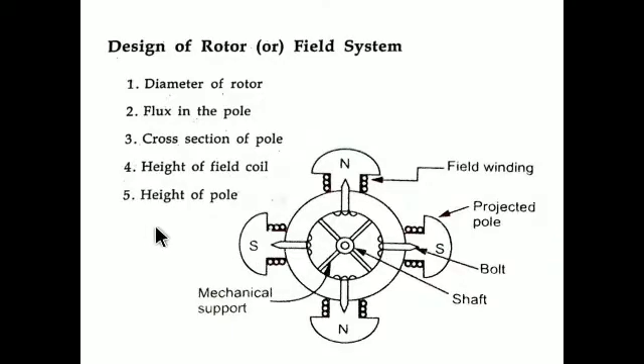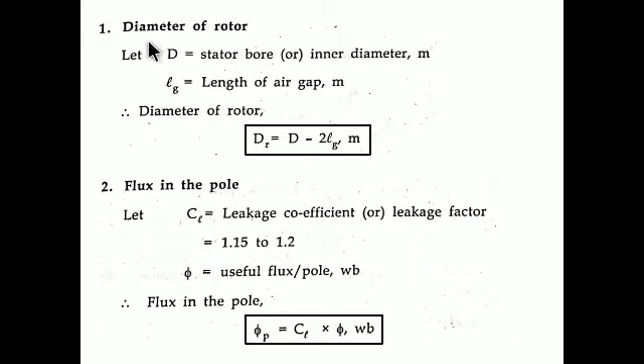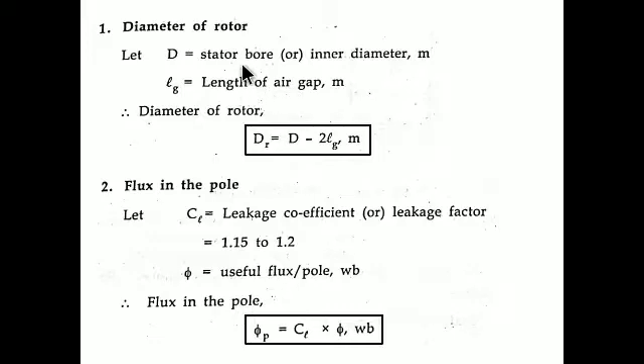The first design step is the diameter of the rotor. There is a direct equation to find it: you subtract two times the air gap length (lg) from the stator bore diameter (D). So Dr = D - 2·lg, where D is the stator bore or inner diameter and lg is the length of the air gap. The factor of two accounts for both sides of the air gap.